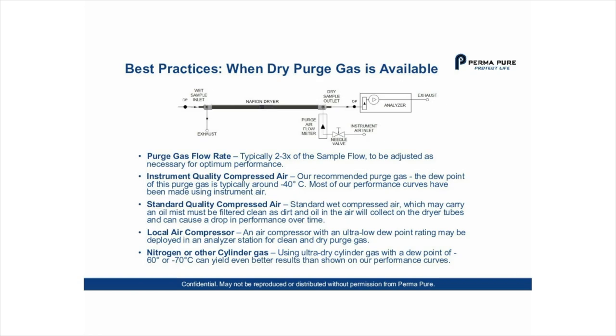You also have the option of deploying a local air compressor. An air compressor with an ultra-low dew point rating may be deployed in an analyzer station for clean and dry purge gas. Many customers use nitrogen or other cylinder gases like argon — sometimes these are carrier gases used in combustion-style analyzers that are then run back as purge gas because it's very cost effective. Using ultra-dry cylinder gas with a dew point of minus 60 or minus 70 can yield even better results than shown on our performance curves, but it is pricey.